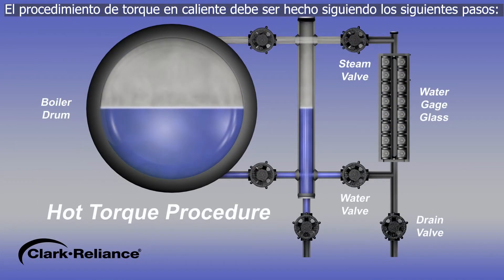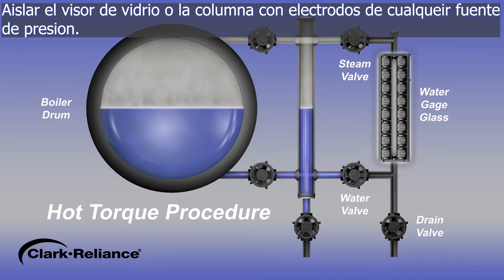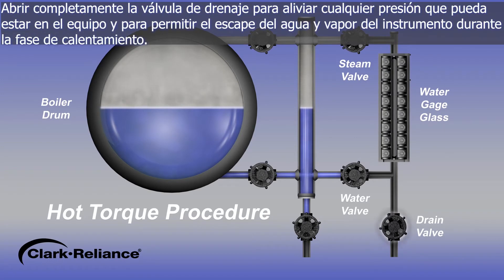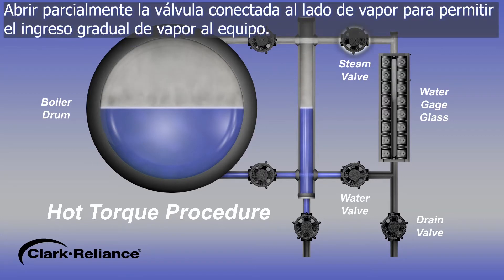The hot torque procedure on a gauge glass or a probe type remote level indicator should be performed as follows. Isolate the gauge glass or probe device from any pressure. Fully open the drain valve to evacuate any built-up pressures and to allow water and steam in the instrument to escape during warm-up. Partially open the steam valve slowly to allow a gradual increasing rush of steam to flow through the equipment.